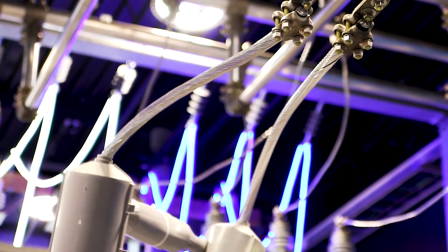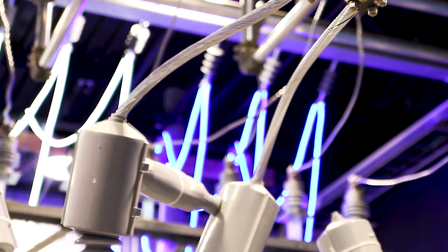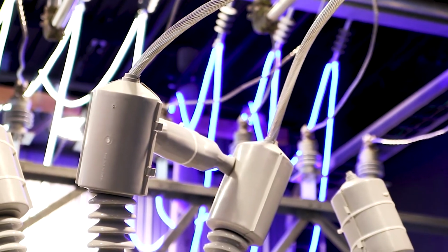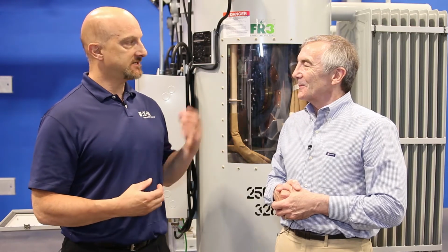So what do you do? Well, it's more around control, and it's more around actually changing the way the regulation is done, and maybe sizing the capacitor banks a little bit differently. For large solar installations, sometimes they use those instead of the capacitor banks to regulate the reactive power flow. So it's really a coordination of efforts. It's not just allowing it to happen, it's actually coordinating all those efforts, working with the control, and making sure the equipment's sized correctly.